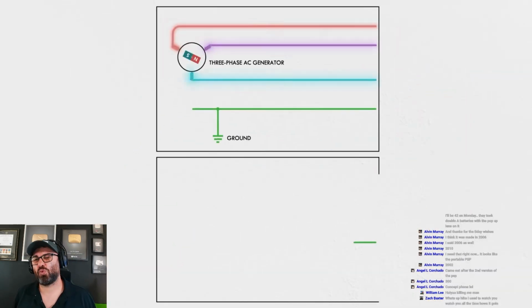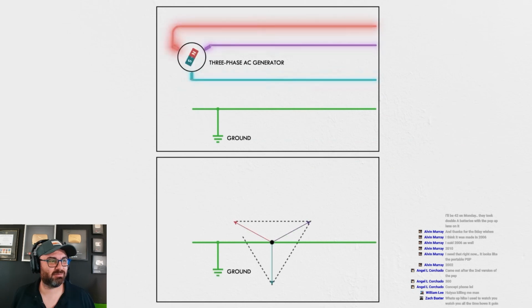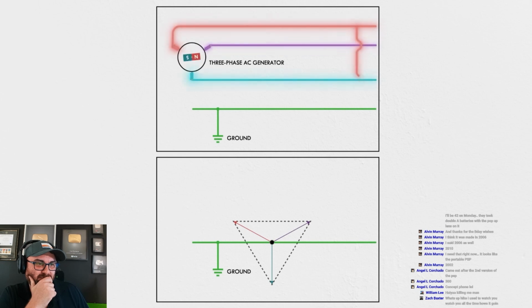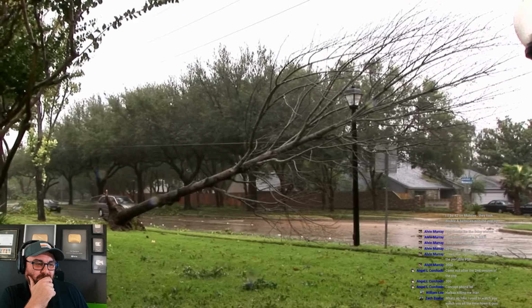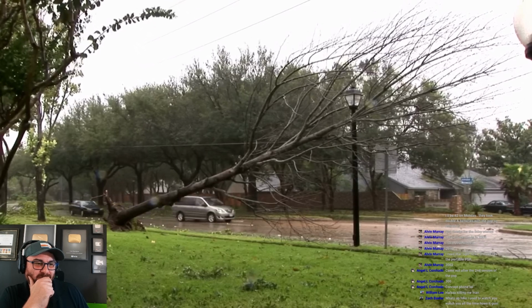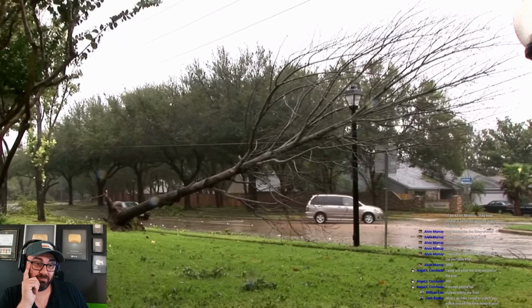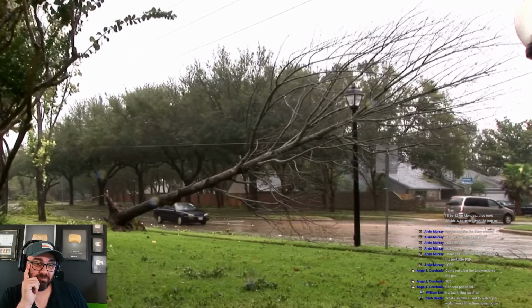Let me put another diagram underneath where distance is equal to voltage. You can see our three conductors all have the same phase-to-phase voltage, and they have the same phase-to-ground voltage too. Everything is balanced. But in this example, that connection to the ground isn't very strong, resulting just from the electromagnetic fields of the alternating current, called capacitive coupling. But watch what happens during a ground fault. This could be a tree branch knocking down a power line, or a conductor being blown into contact with a steel tower, or any other number of problems that lead to a short between one phase and ground.